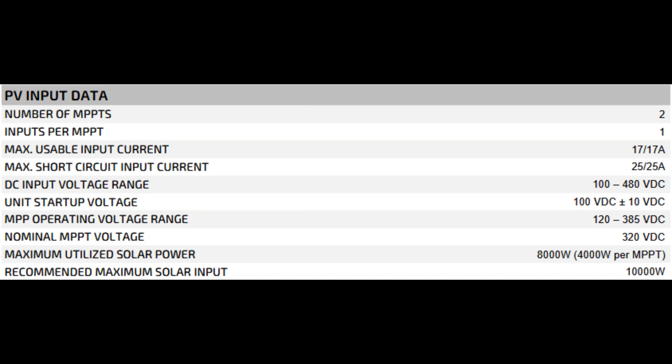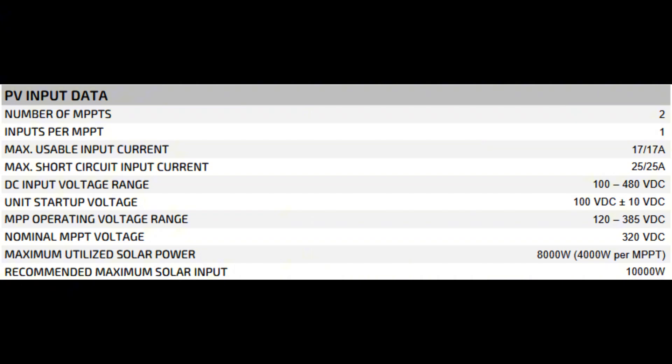Here's where you see the real flexibility for solar. Two MPPTs means there are two separate maximum power point tracking channels. Each tracks and optimizes the output from a string of solar panels independently. This is especially helpful if you have panels on different roof angles or partially shaded arrays. The DC input voltage range of 100 to 480 volts DC is huge. You can configure your panels in series so the voltage is high, minimizing wire losses.